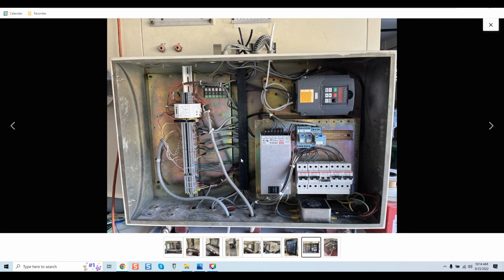When I say a slight degree, it's never as effective as actual filtering, when we're using an actual tin-braided copper braid or Mylar foil, or for that matter, even more active passive filtering like a ferrite, okay? This is not the way you want to wire this. You can see these leads are really long, and the longer these leads are that are not shielded, you do have potential for issues with EMI.